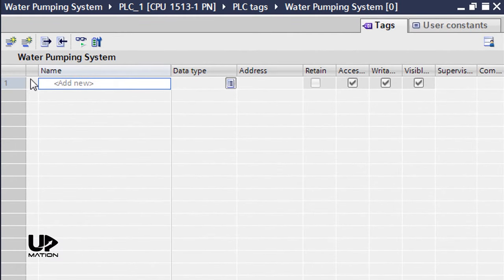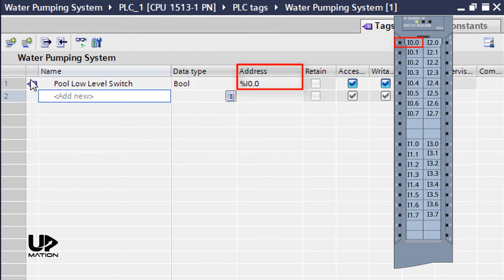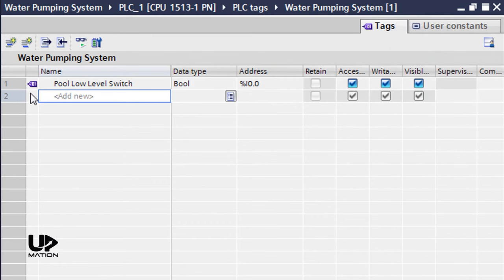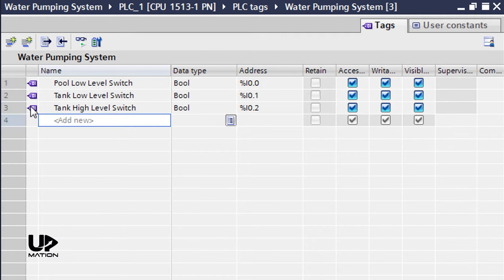The first input is the Pool Low Level Switch. By pressing Enter, the software automatically assigns the I0.0 address to this input, which is the first channel of our only DI card. The next one is the Tank Low Level Switch with the address of I0.1. And the last input signal is Tank High Level Switch with the address of I0.2. Finally, there is our only output which I will name as Motor-Pump.